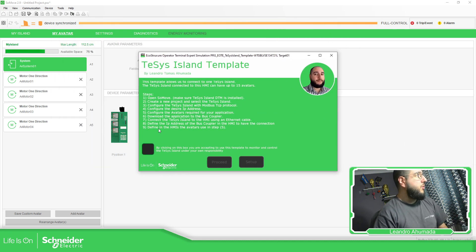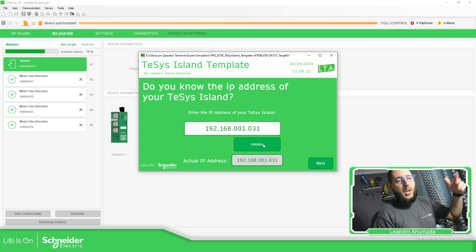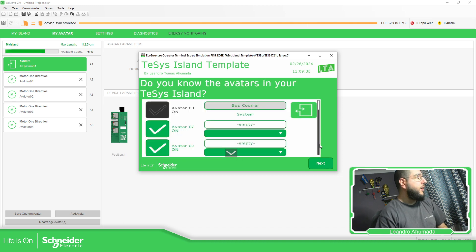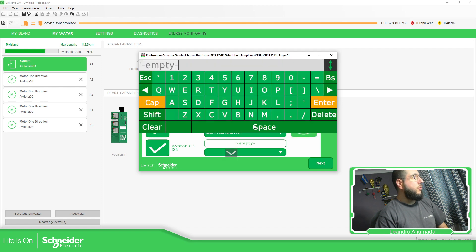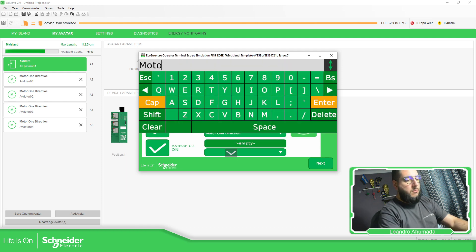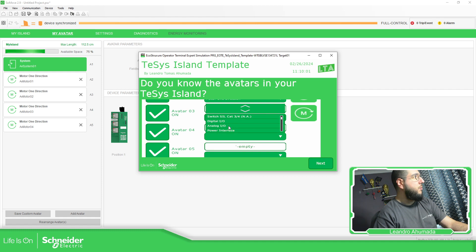This is the template with steps you can easily follow. First, we just need to validate the IP address of the Tesys Island — in my case it's this one, but you can validate and it will update everything in the HMI software. Next, we need to define our configuration: I'm going to select motor one direction for motor one, and motor one direction for motor two. You just need to replicate the same configuration you already have.